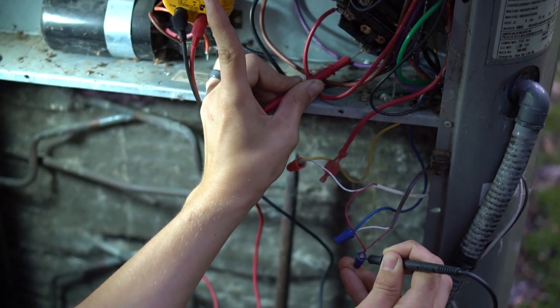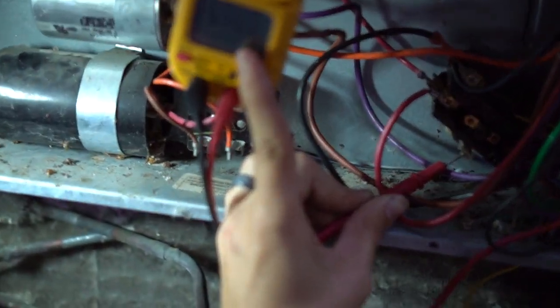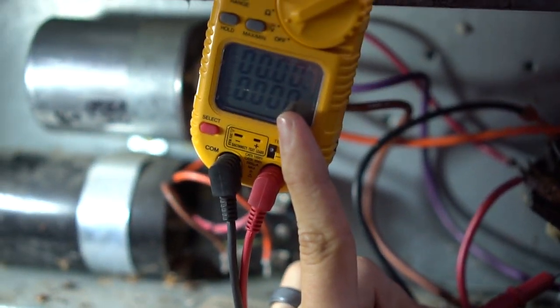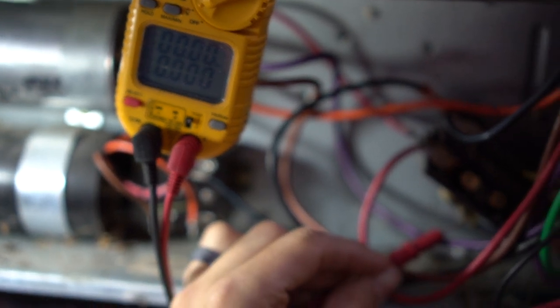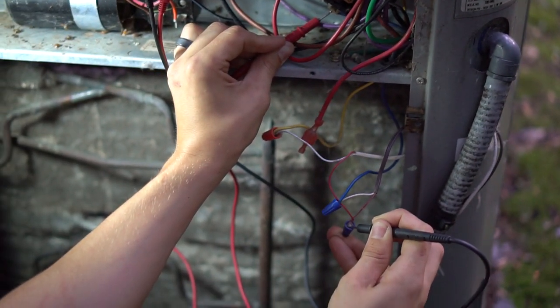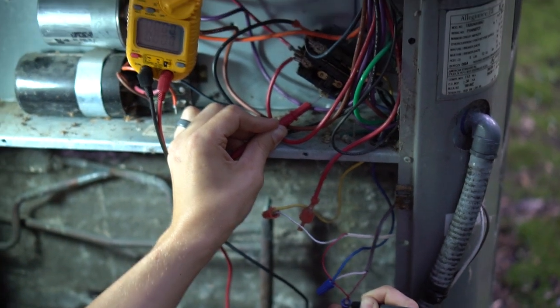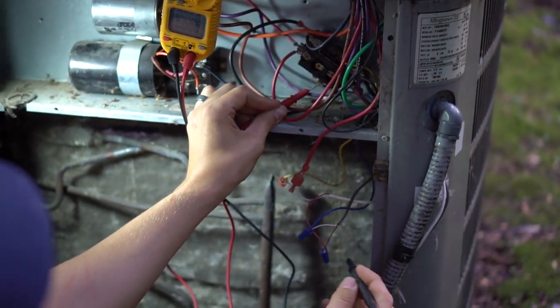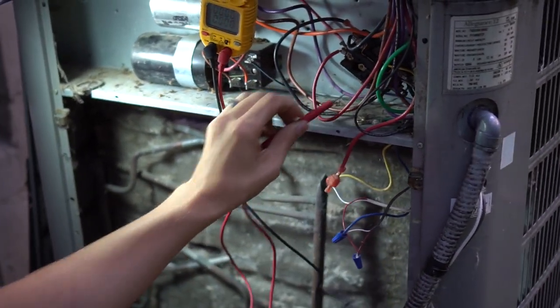I have zero volts right here, but that's because my thermostat is off right now. If your thermostat is calling for cooling, you should have 24 volts here. So once you verify that you have 24 volts coming from your furnace, then you just have to verify if that voltage is going out of the power saver switch.